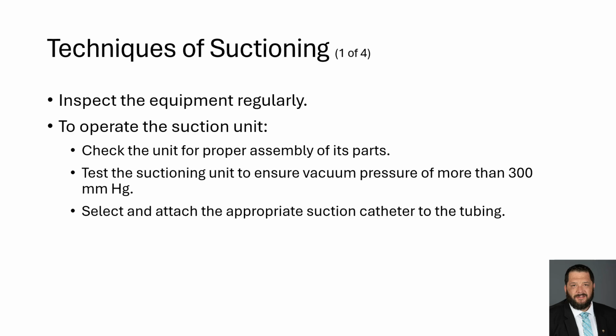Make sure for your suction equipment, you're inspecting the equipment regularly. This should be performed at least daily, and make sure that your suction, when it's creating a vacuum or the suction is turned on, is creating a vacuum pressure of more than 300 millimeters of mercury.